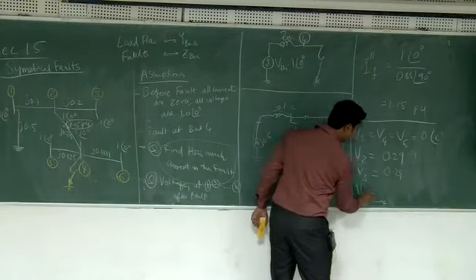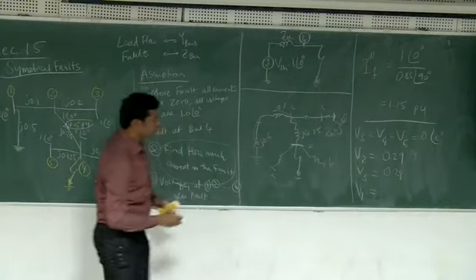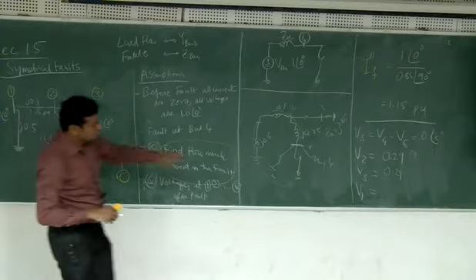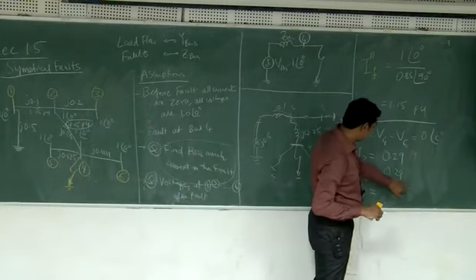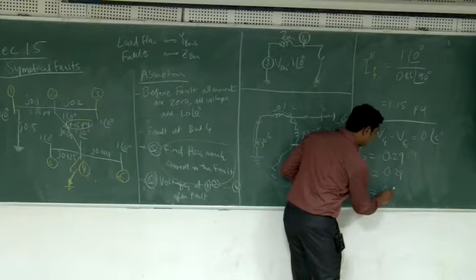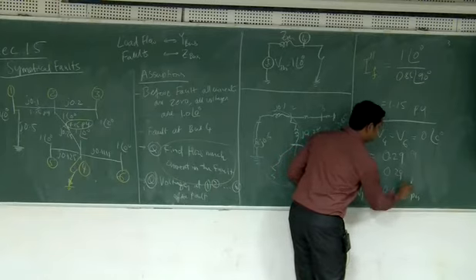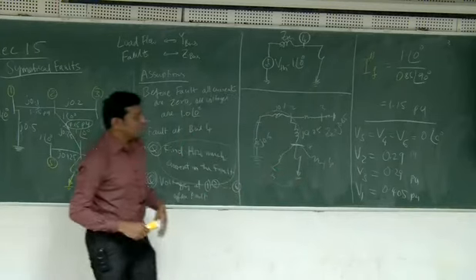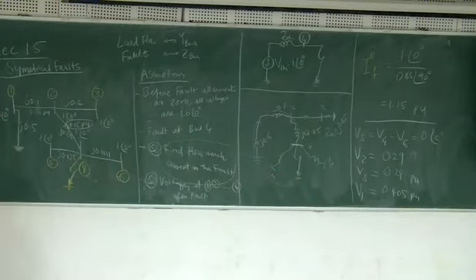So what is voltage at bus 1? The current here is 1.15 per unit, and the same current is flowing like this. That current multiplied by 0.1 is the voltage drop, and you add it to this to get the voltage at 1. So 0.1 times 1.15 is 0.115. Add 0.115 to 0.29, and you get 0.405 per unit. So like this I can get the voltages at different buses at that fault.